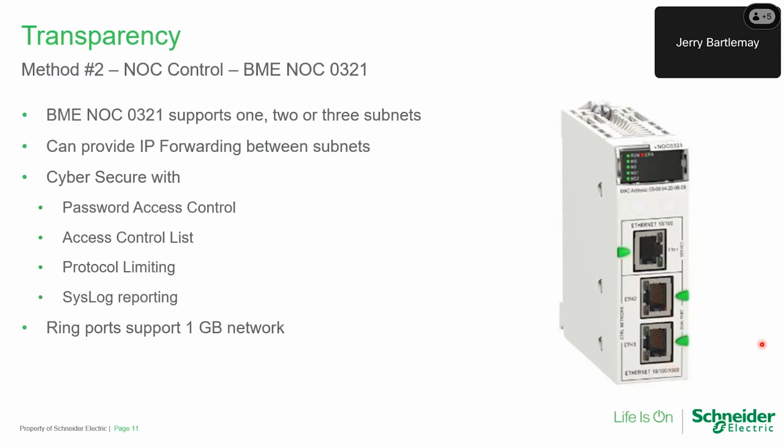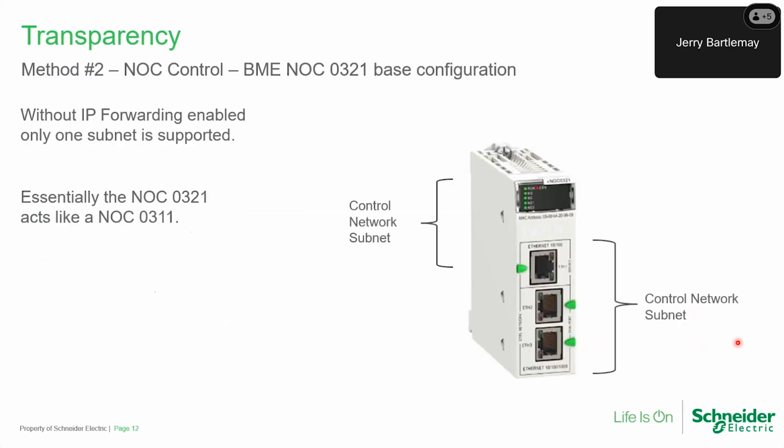And so if you're connecting them to a plant network directly, that's 1 gigabit, which is happening more and more frequently. These are configured for RSTP. So we can create a plant network around that and basically just daisy chain our controllers as part of that plant network, or connect them up to a switch, which is most common.